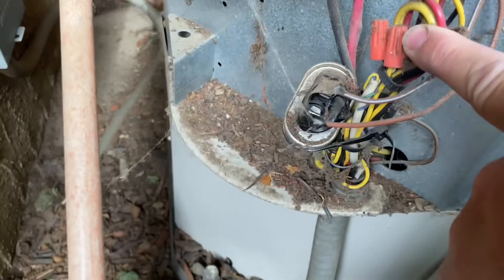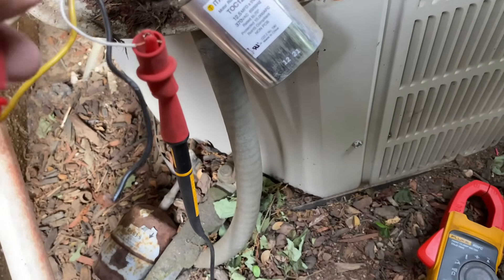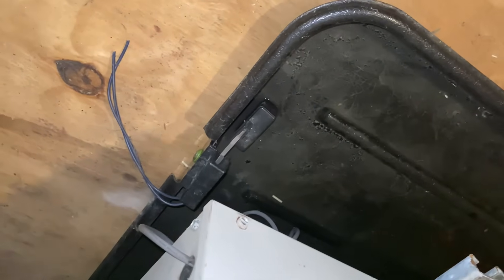Contactor not pulled in. They made it very tight here. No voltage. Now we go to the thermostat — R and Y — jump down. Still only 2.8 volts. Water in the float switch, but float switch is not activated. Is there another float switch I'm not seeing here? There's got to be something here. Bingo. There it is. A good technician is observant of their surroundings. Remember that, guys and gals.